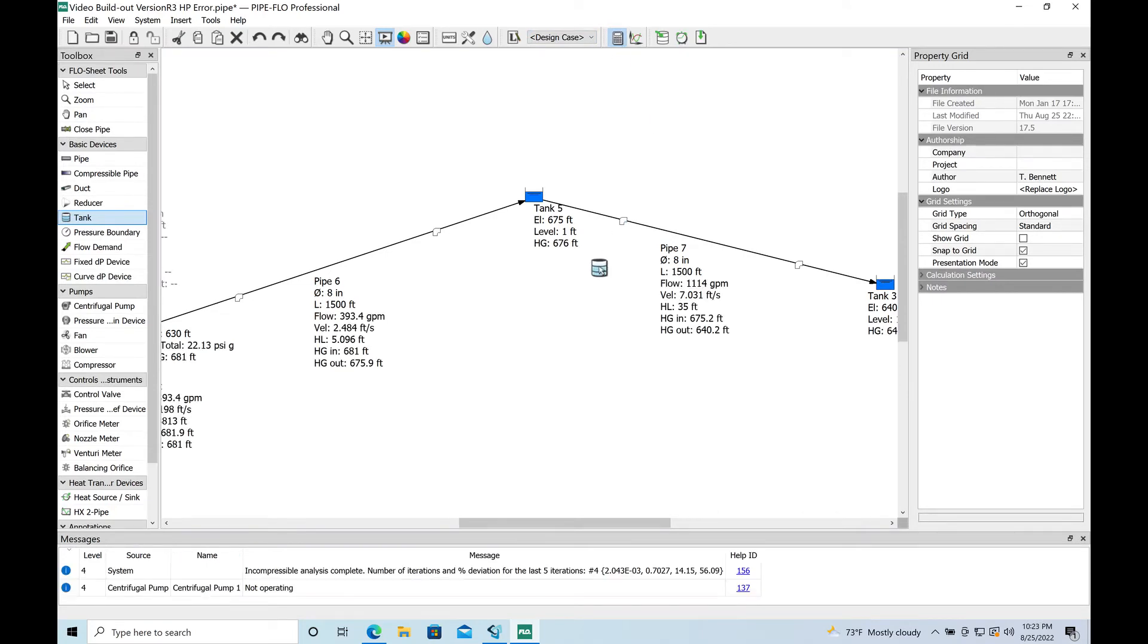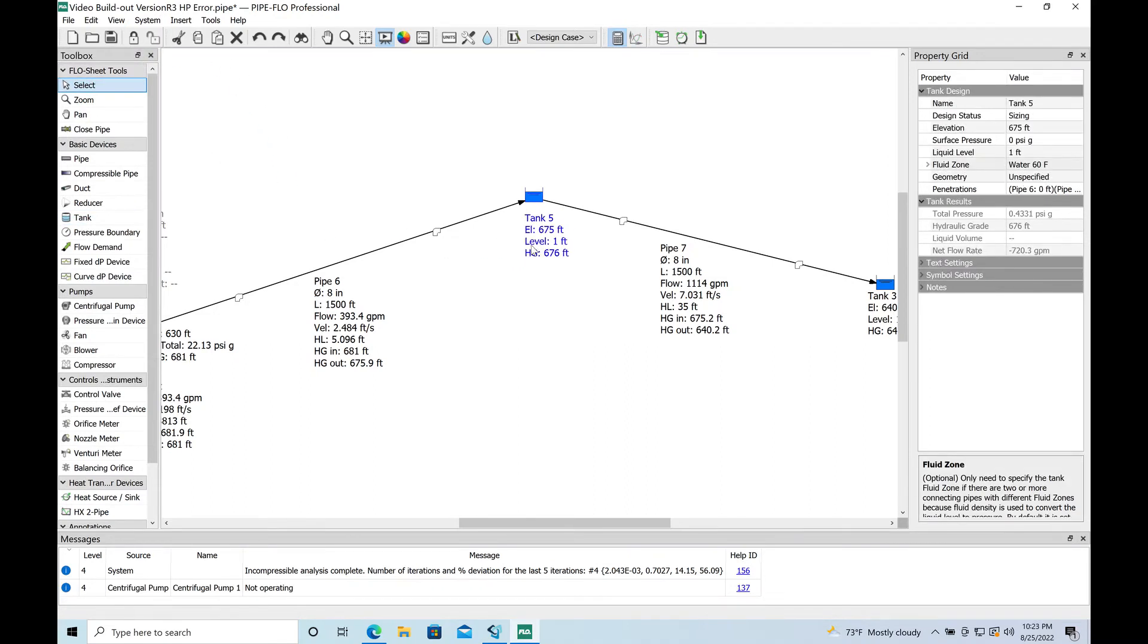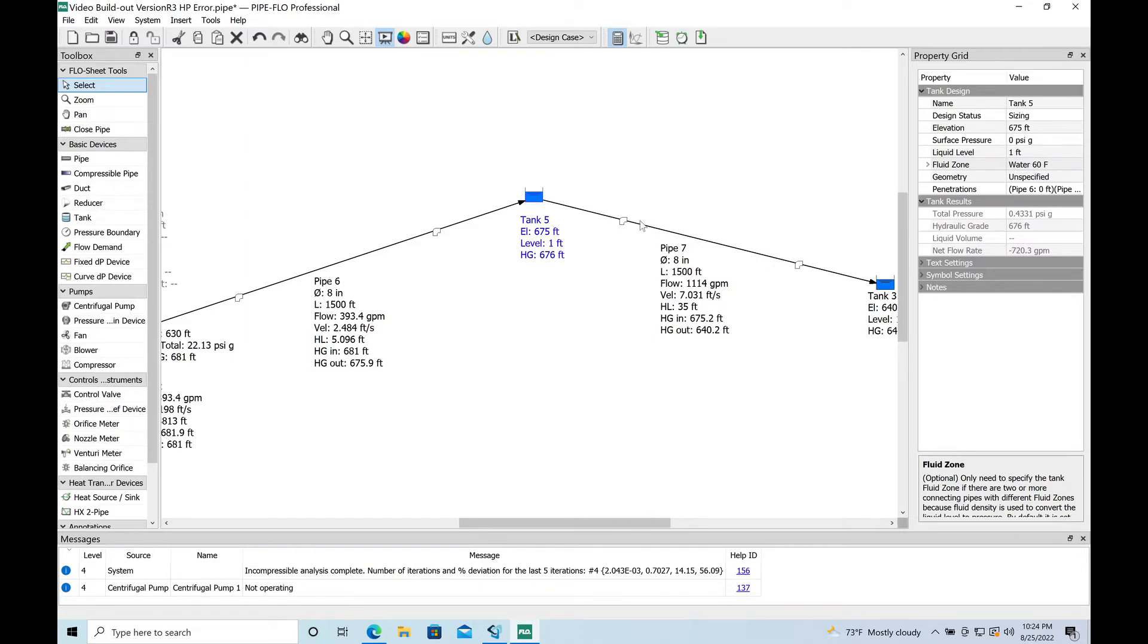And it does, as you can see. Now we're pretty much back to where we were. This tank is actually operating a lot like an air release valve. It's allowing the water to break pressure here and then drain by gravity.